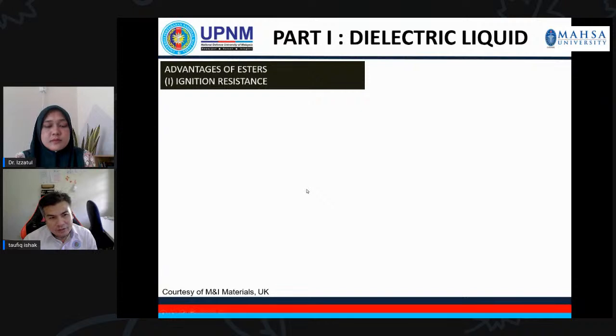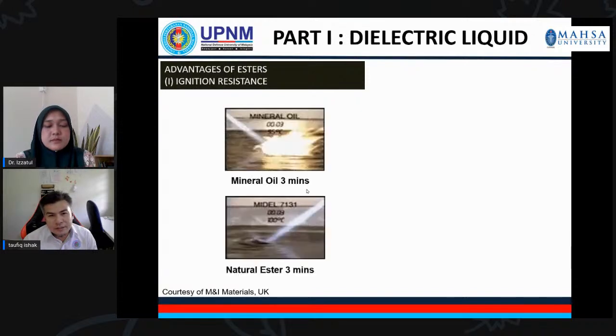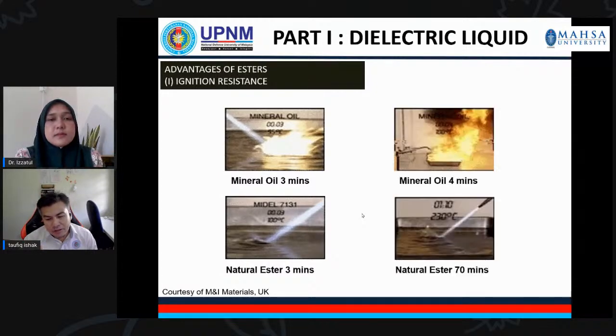The second one is related to the ignition resistance of vegetable oil as compared to mineral oil. As you can see from the picture, mineral oil only took 3 minutes for fire to ignite as compared to natural ester. When you apply the fire, even after 3 minutes at 100 degrees C, still no fire is ignited. That's quite interesting.